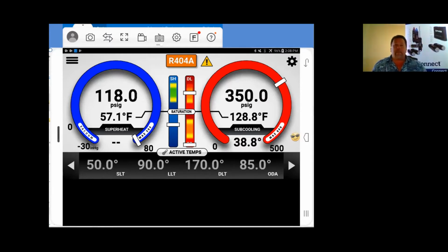Now, this system that I'm showing you on the screen right now is a 410A system. So we've got our pressures, our temperatures, we've got everything shown here. We've got our performance, that's our split. We don't have tonnage, we don't have BTUs, we don't have EER or anything like that. This is just simply what you're reading when you hook up the system, whether it's an iManifold or an iConnect.